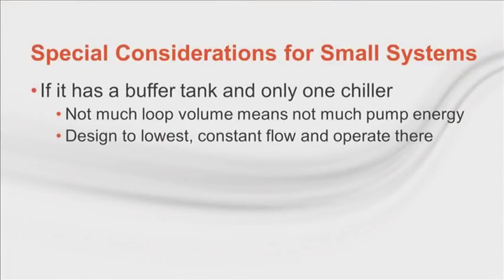I've been brought into projects doing variable flow when there is only 10% turn down before the chiller reaches minimum flow, and it may only have 1 or 2 air handlers. This is not a good application. I like to think that if a system is small enough to need a buffer tank, then the pump savings from VPF are pretty small. So then we're down to lower first cost, saving a pump. Constant flow systems have only 1 pump. If the flow is already low, variable primary flow may not be the right way to go. We like to see at least 40% available system flow turned down before considering variable primary flow.